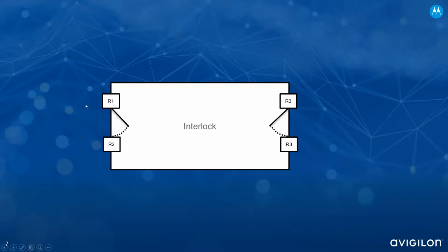So if you want to scan into reader 1, we need to make sure this door is closed. And also if you want to go out reader 2, so if you're already in the interlock and somebody opens up this door, you don't want them to be able to open this. And of course, vice versa, if this door is open reader 1, we don't want people to be able to come into the airlock from reader 3 or exit from reader 4. Again, sorry, that is mislabeled. So we want to make sure the opposite door is closed.